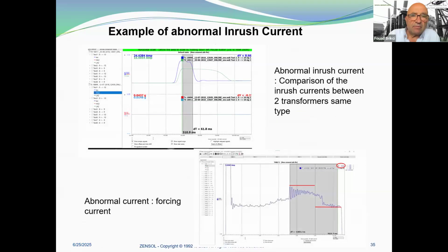We also have examples of abnormal inrush current. Here it's the comparison of two inrush currents between two transformers of exactly the same type. The one on the bottom, the green signal, shows that there was a problem. It was a brand new tap changer. And here the current is forcing at the end, exactly like the previous cases.